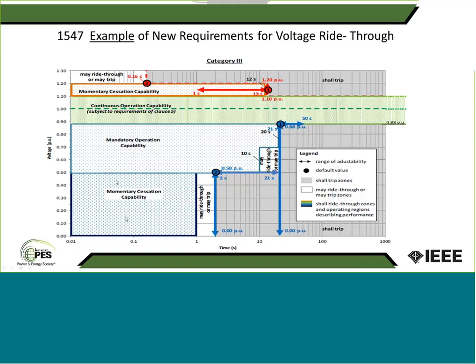And the other area that has been introduced in the new standard is called momentary cessation capability. This is mainly applicable to categories 2 and 3. The idea is that inverter-based technologies have this capability: when the voltage goes below a certain limit, in this particular case as a default 50%, inverters stop producing current, but they're not physically disconnected from the grid. So once the voltage recovers and goes back above 50%, they can start producing current immediately.